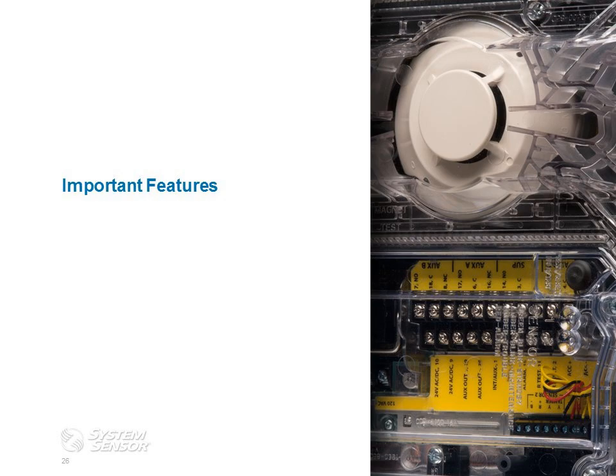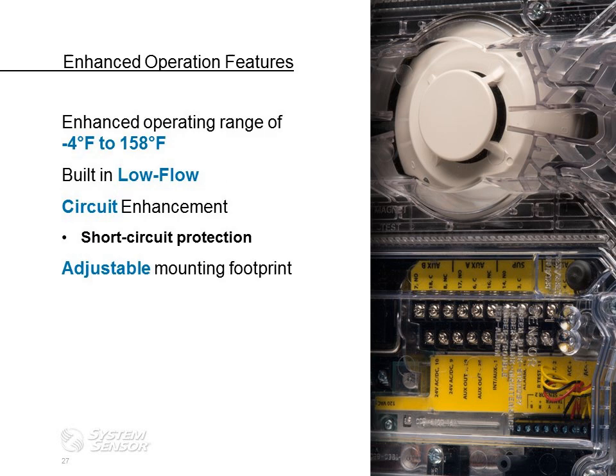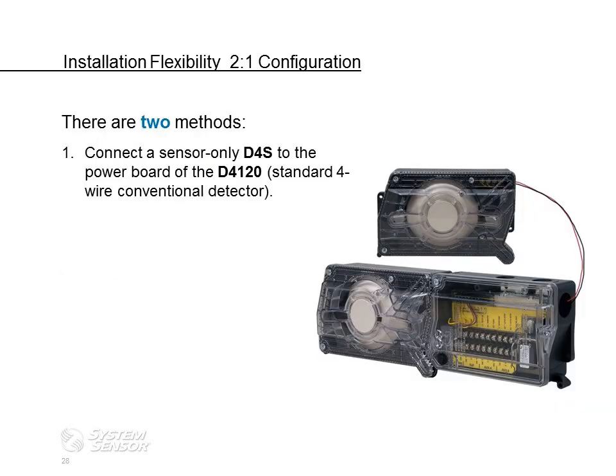Some important features about the product. The enhanced operation features, it has an enhanced operating range of -4 to 158. It has built-in low-flow circuit enhancement. Our duct detectors will operate from 100 to 4,000 feet per minute for airspeed out of the box. And the duct detectors that we provide and offer have an adjustable mounting footprint. We do something that's unique to the market as well in offering installation flexibility by allowing for a 2-to-1 configuration.